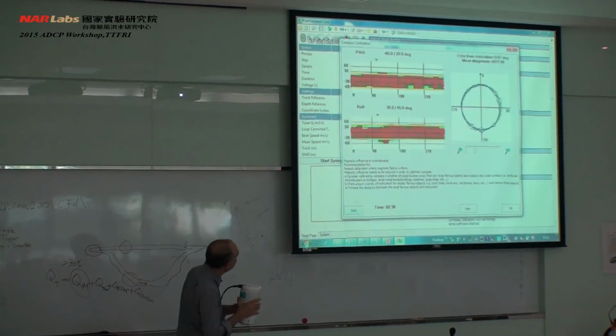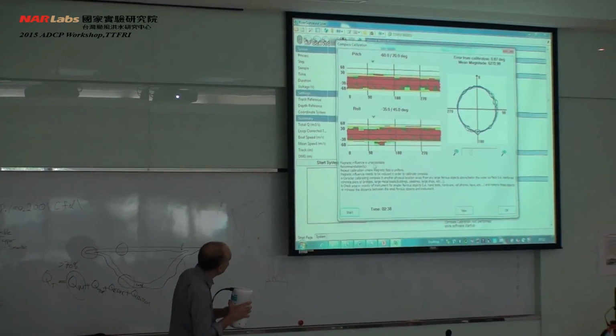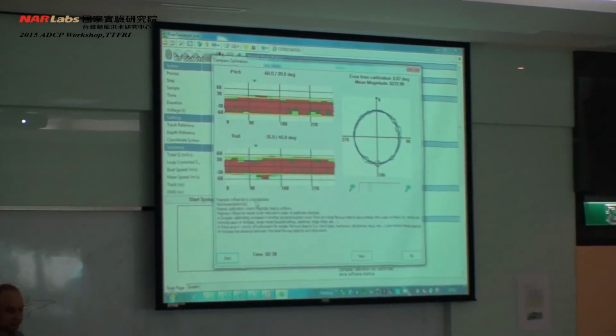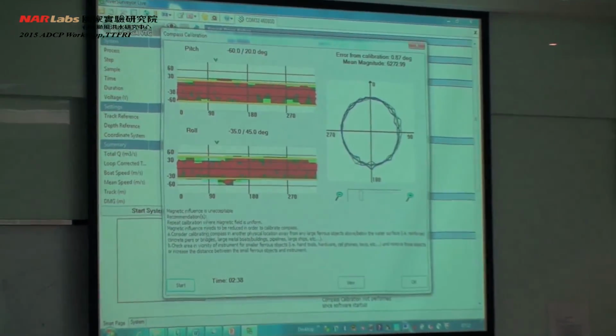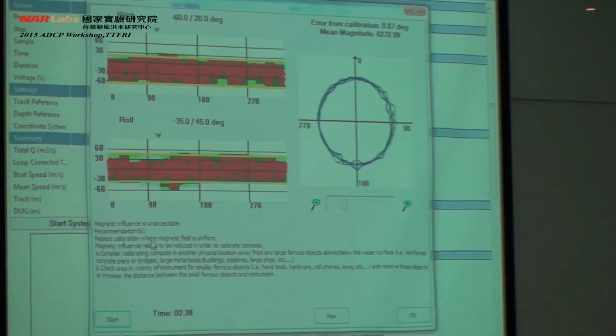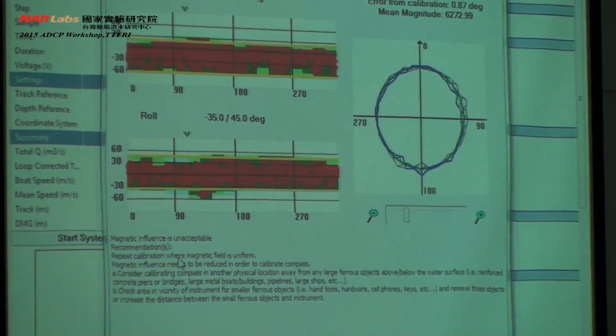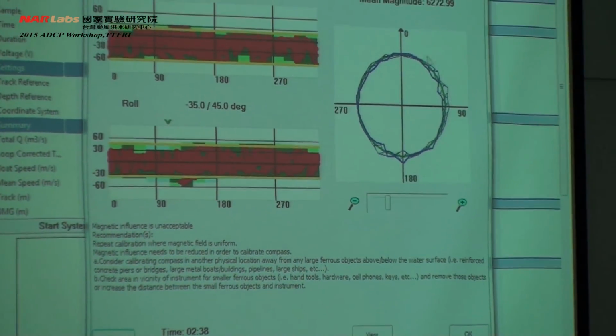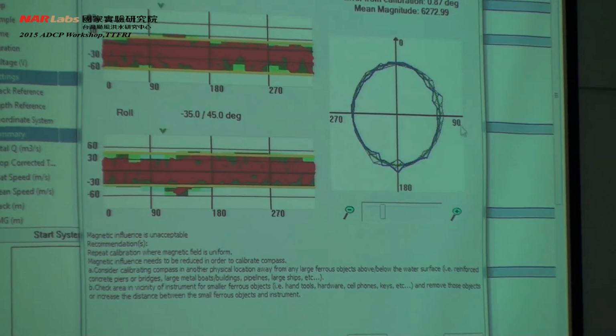And it comes up here, it tells us that the magnetic influence is unacceptable. The recommendation is to repeat the calibration where the magnetic field is uniform. You'll see here, this actual circle now is giving us a result.